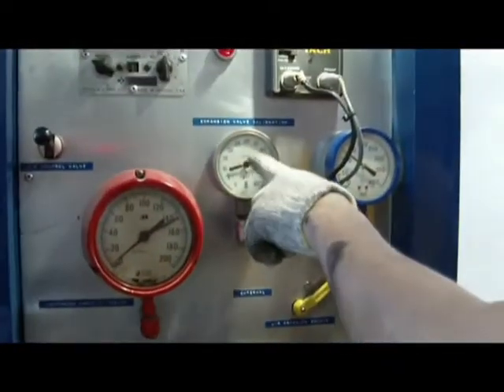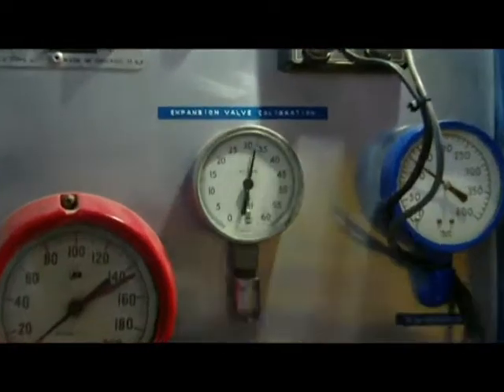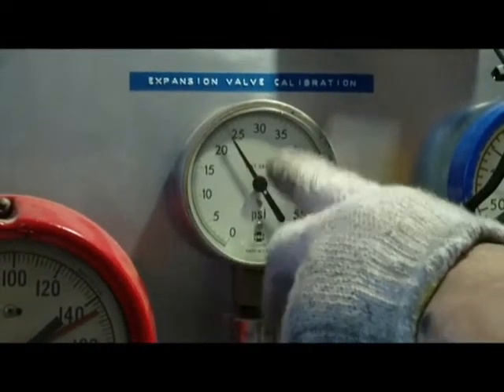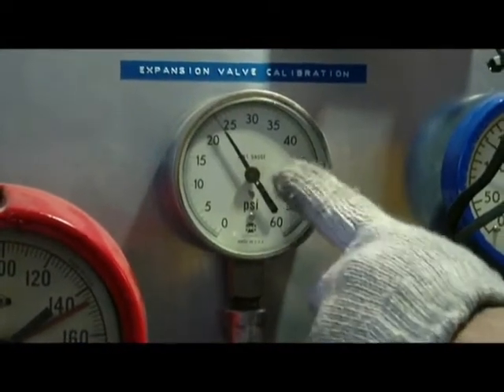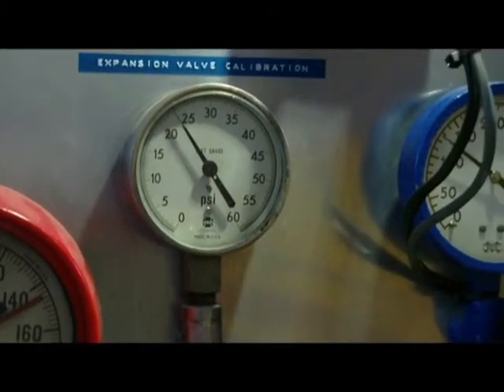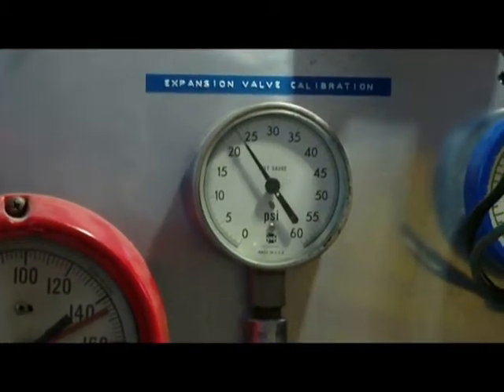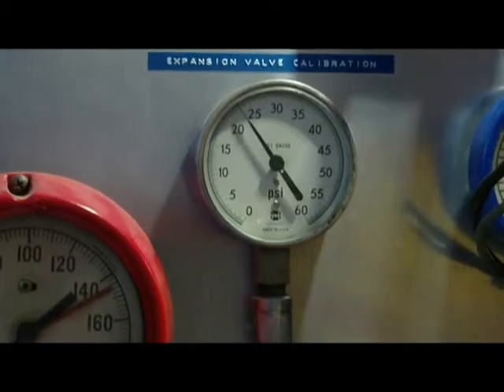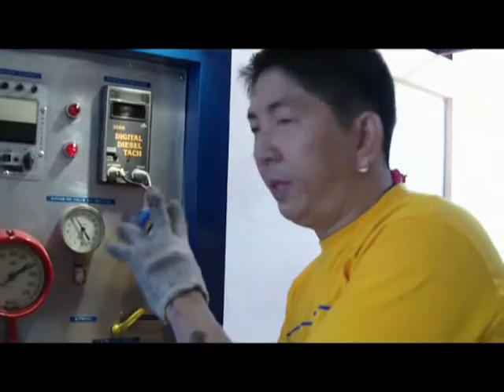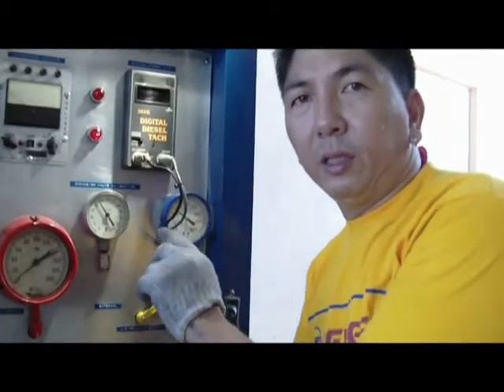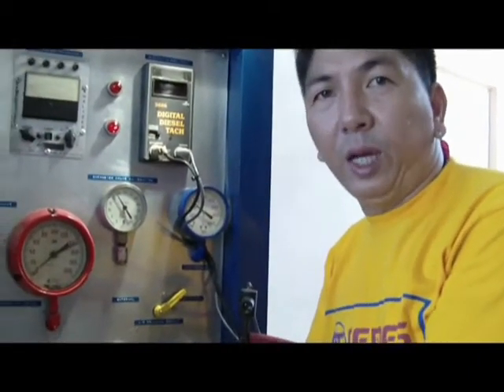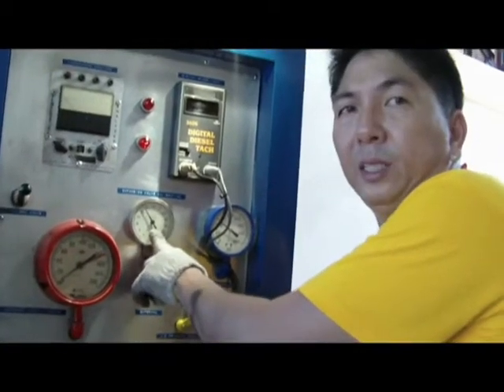you will see it will already work inside the diaphragm of this valve, and it will read whatever setting you made. As you can see, it's now in 23 because I've adjusted it counterclockwise. You cannot adjust an expansion valve if you don't have this machine, because it will only aggravate the situation. You don't know the reading while just rotating this adjuster here without having a gauge like this one.